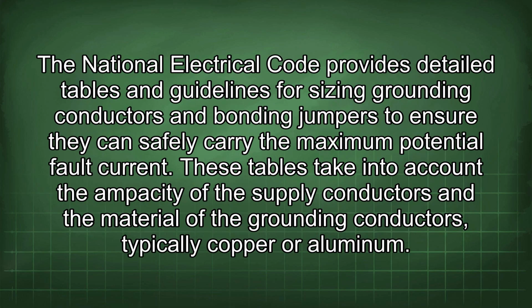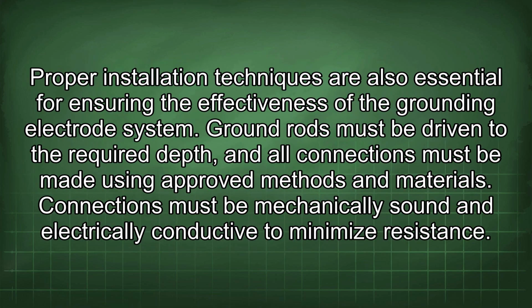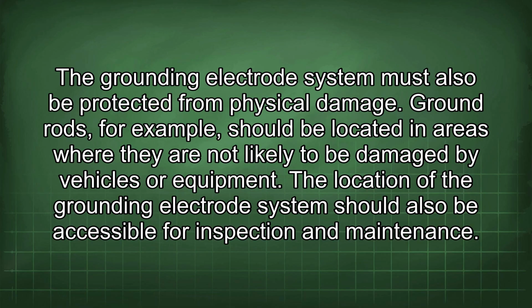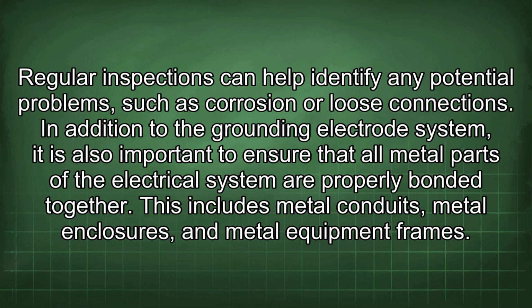The National Electrical Code provides detailed tables and guidelines for sizing grounding conductors and bonding jumpers to ensure they can safely carry the maximum potential fault current. These tables take into account the ampacity of the supply conductors and the material of the grounding conductors, typically copper or aluminum. Proper installation techniques are also essential for ensuring the effectiveness of the grounding electrode system. Ground rods must be driven to the required depth, and all connections must be made using approved methods and materials. Connections must be mechanically sound and electrically conductive to minimize resistance. The grounding electrode system must also be protected from physical damage. Ground rods, for example, should be located in areas where they are not likely to be damaged by vehicles or equipment. The location of the grounding electrode system should also be accessible for inspection and maintenance. Regular inspections can help identify any potential problems, such as corrosion or loose connections.